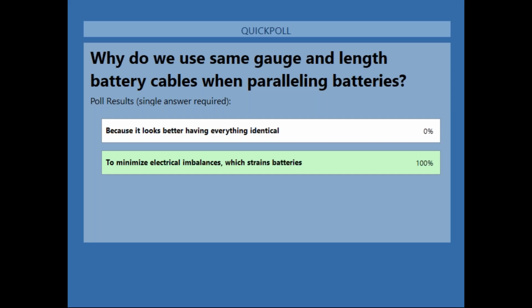Let's go to our next slide, showing a bunch of batteries in up to 5 strings. Normally I do not recommend this, but sometimes you have to. These are already 8D batteries, the big 250 to 300 amp hour batteries. So sometimes you have to. If you do, you want to follow some rules when paralleling batteries to minimize these imbalances. We're going to go into those rules in just a minute.